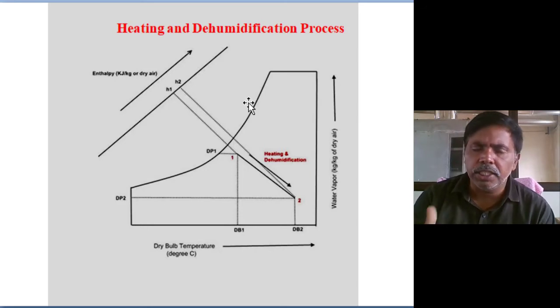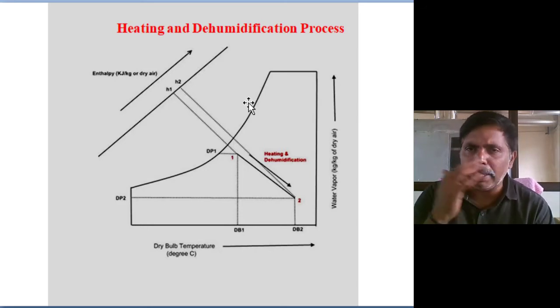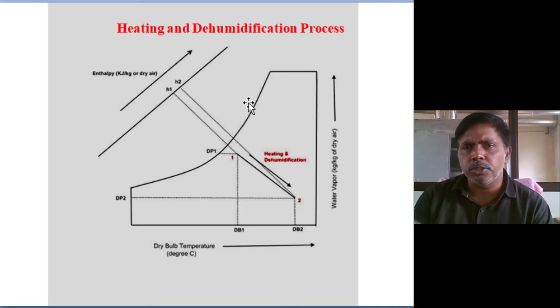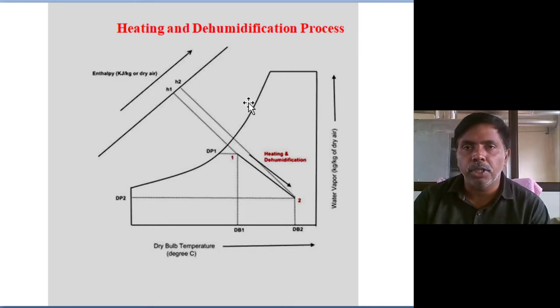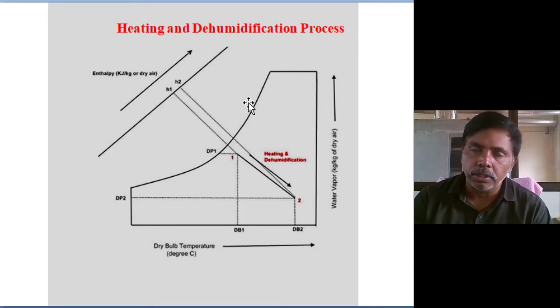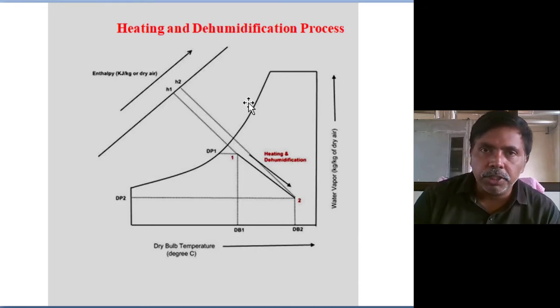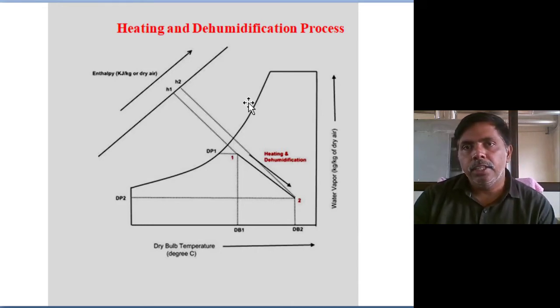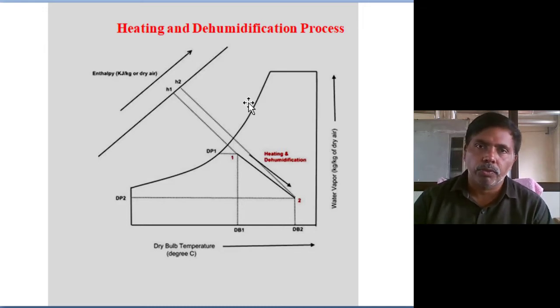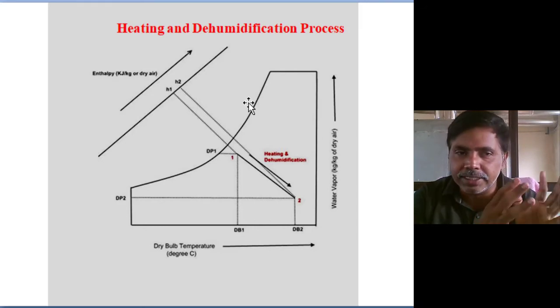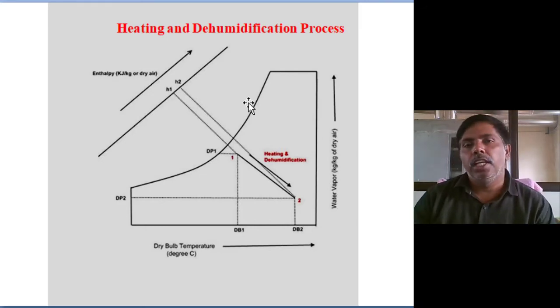For any costly items, electronic goods, bags, or dress materials, at present a silica gel packet is common, because it will not allow moisture inside the pack. It will absorb the moisture in the air. That's all. But for air conditioning, recycling of the system is required. At 160 to 180 degrees temperature, it will release whatever moisture was absorbed. So it is a cyclic operation. These are the 6 methods we are using for year-round air conditioning systems.